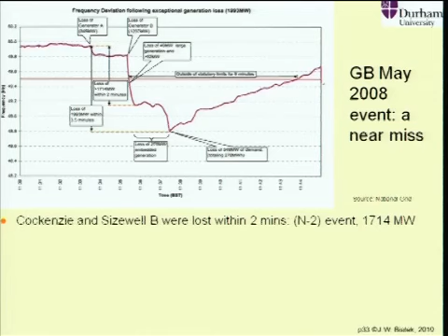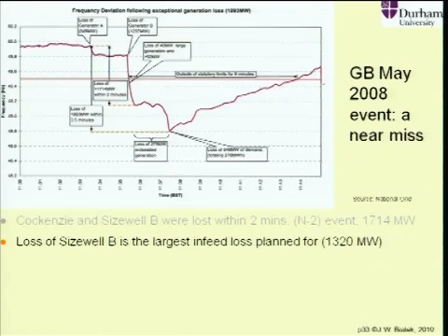So you can see here first Cockenzie dropped, and there's a slight drop in frequency because Cockenzie is small, it's 345 megawatts, and then a huge drop in frequency due to dropping of Sizewell B. Sizewell B is nearly 1300 megawatts. So we were down over here, and initially we lost 1700 megawatts, over 1700 megawatts. Now, remember, I've told you that the system is designed to be n-1 secure, and this n-1 means Sizewell B, then it is secure against the loss of 1320 megawatts. More than that was lost.